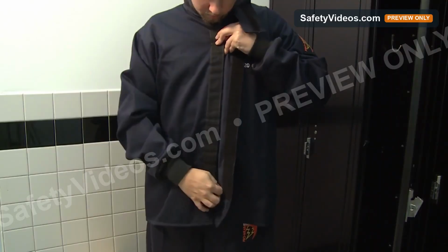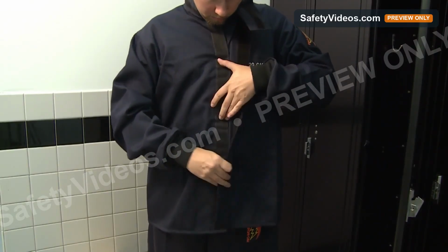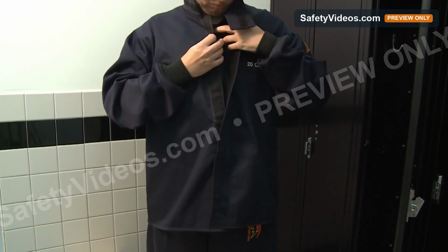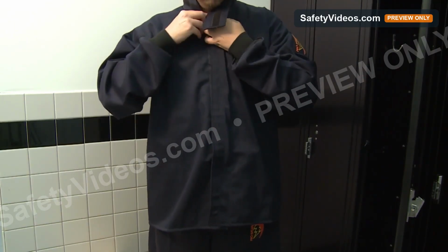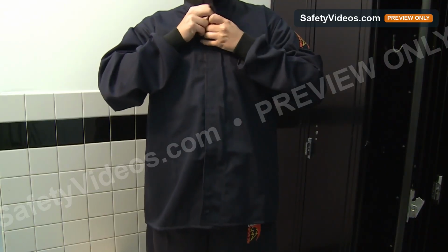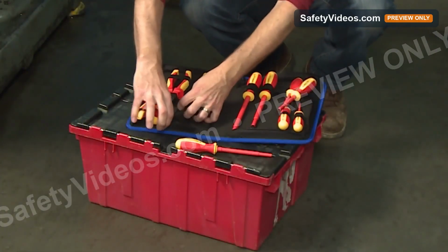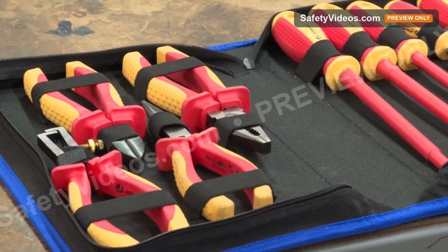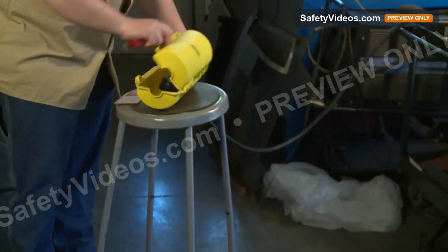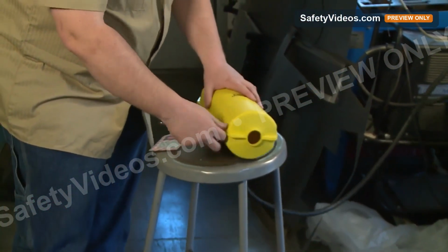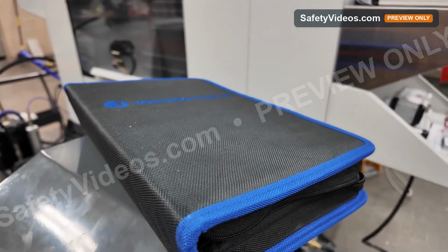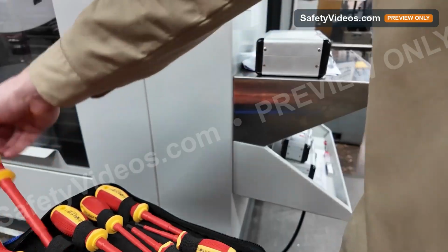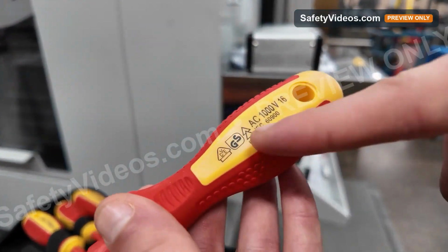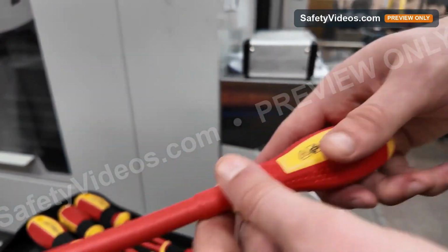Regardless of the type of PPE you wear, it's important that it has a loose fit to provide additional thermal insulation and it fully covers your body. But even with all these precautions, you aren't done yet. It's also important to use the right tools and protective equipment when you're working around electrical hazards. Any tools that you work with within a restricted approach boundary area should be insulated and need to be rated for the voltages they are being used with.